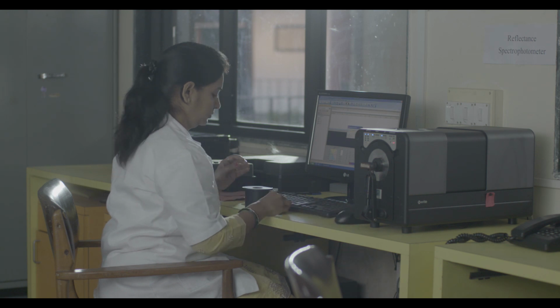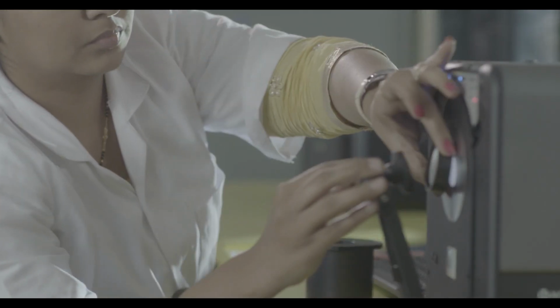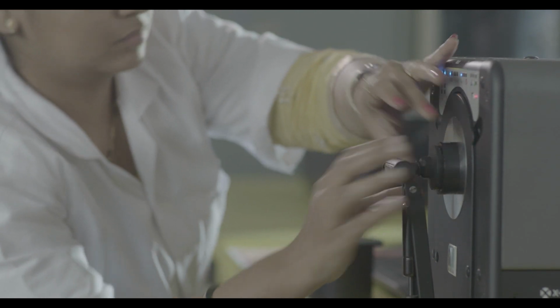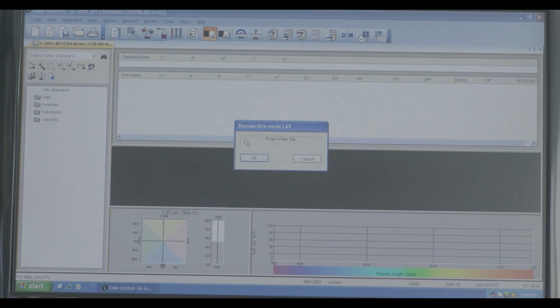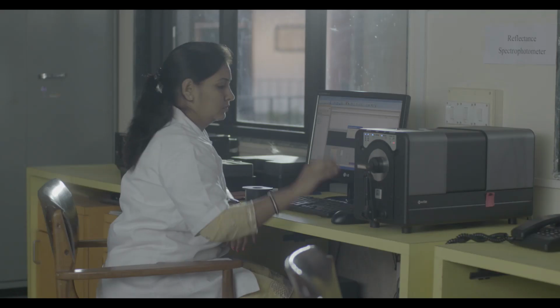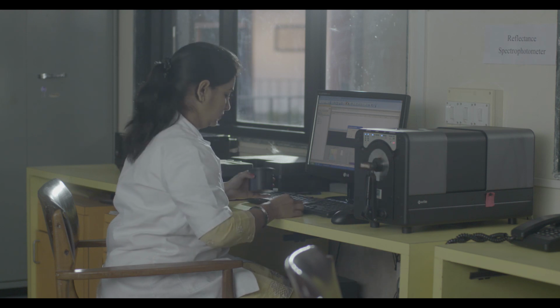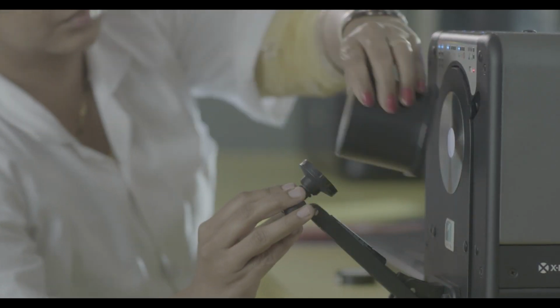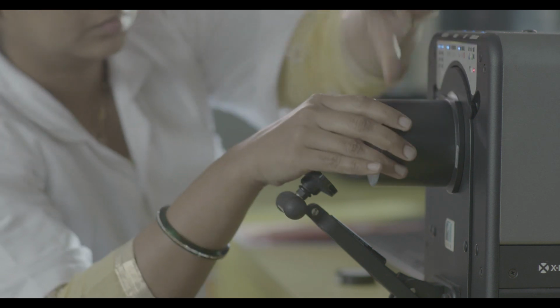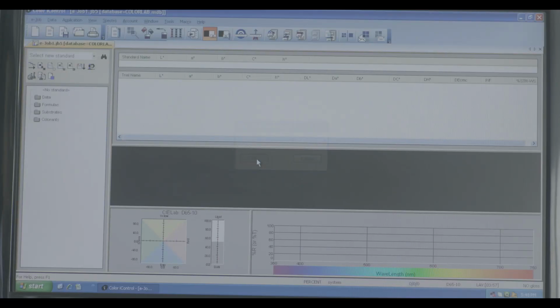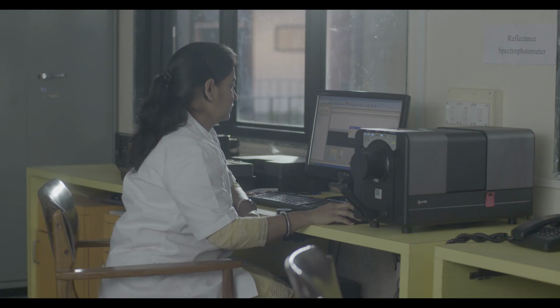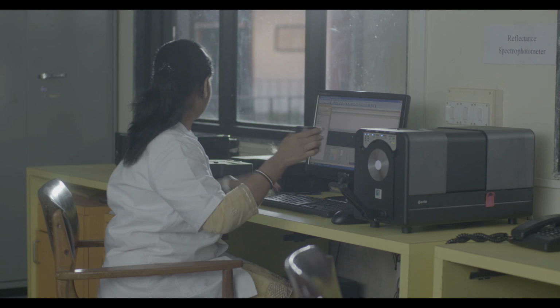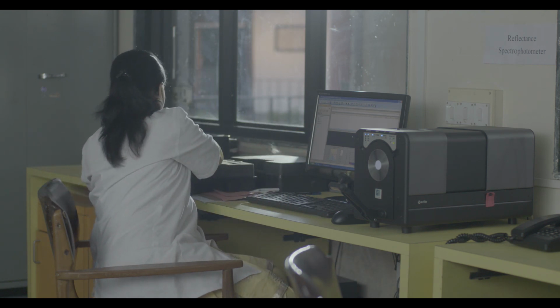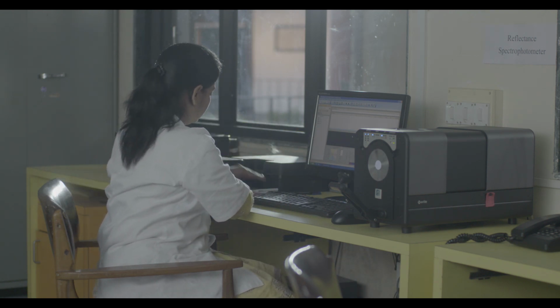Open the sample arm by grasping it and pulling it towards you. Place white tile at the viewport and close the sample arm. Select Calibrate Spectro option and click on OK. Then remove the white tile and place the black trap in viewport and click on OK. Now calibration is complete and the recalibration will be required after 4 hours. Place the white tile and black trap back in the kit.